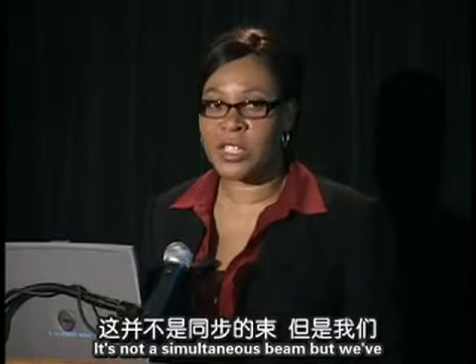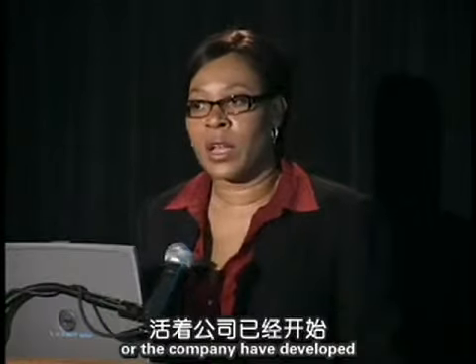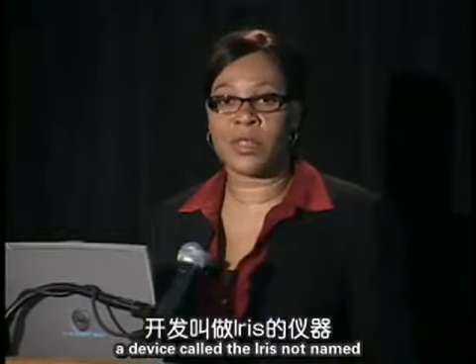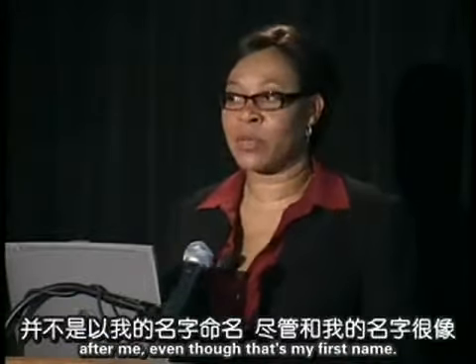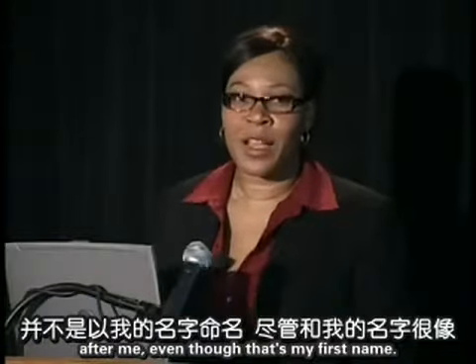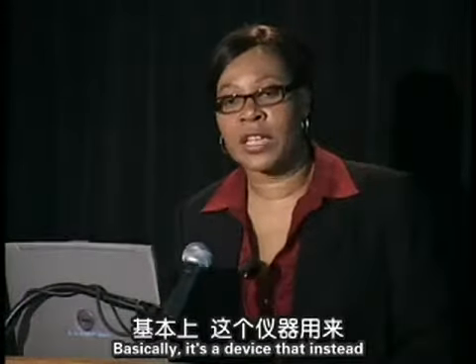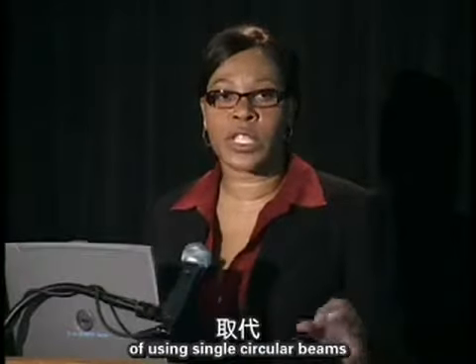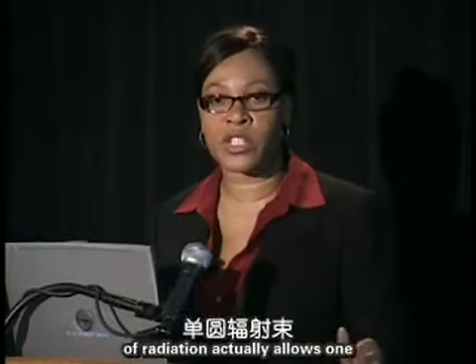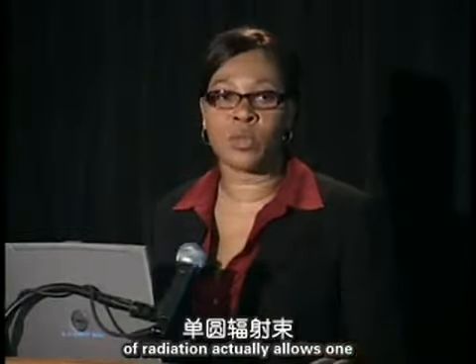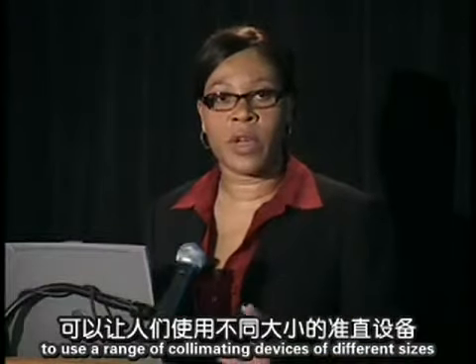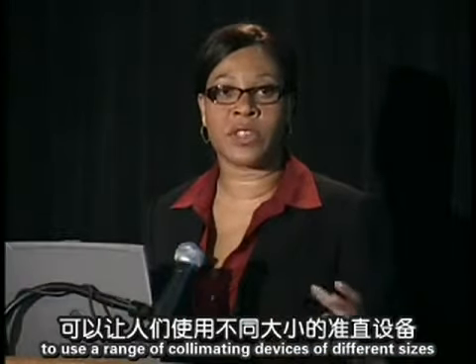It's not a simultaneous beam, but the company has developed a device called the Iris, not named after me, even though that's my first name. Basically, it's a device that instead of using single circular beams of radiation, allows one to use a range of collimating devices of different sizes.